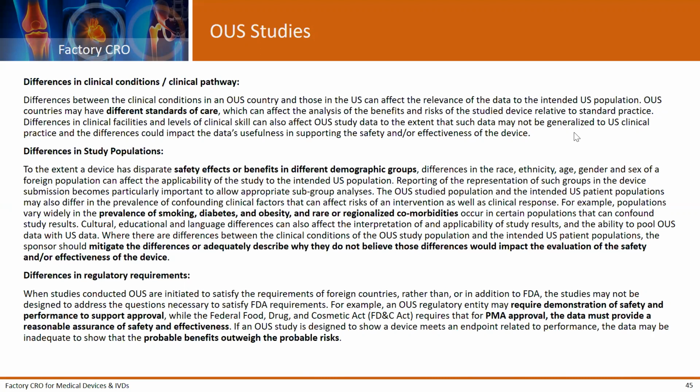Going on to questions here, one of the questions at the beginning was, 10 to 15% of all 510K submissions do not require a clinical study. What determines if you need a clinical study? I think you did a great job of answering that in slide 30, at around 34 minutes in the presentation. If anybody has questions further, one of the things I would point them to is that some of the product classification codes actually have special controls guidance documents that will specify when you would need a clinical study and when you would not need a clinical study.